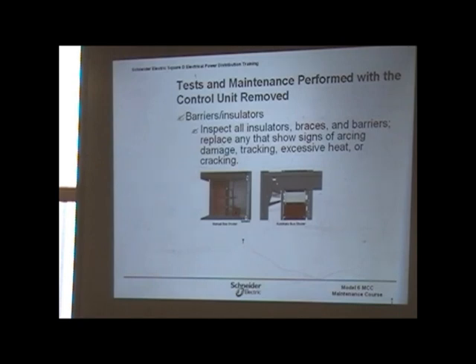That's why we discourage people from this. We, as the manufacturers, are prohibited from working on any energized equipment at all, or breaking the plane. Our hand cannot break the plane of energized equipment unless we're dressed up for it and have the proper PPE. If we're troubleshooting in a control power section, even though it's 120, we have to do an arc flash analysis to make sure that we have the proper PPE and properly rated equipment before we start working on anything or sticking our hands into it. Because if I go in there with a screwdriver and haven't even done an arc flash analysis, it's grounds for termination.